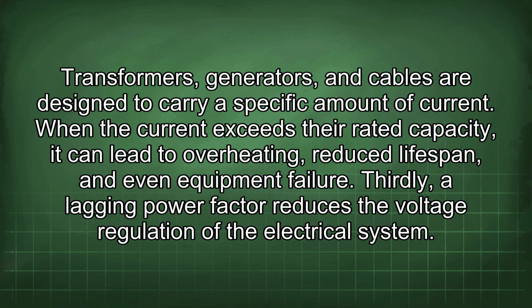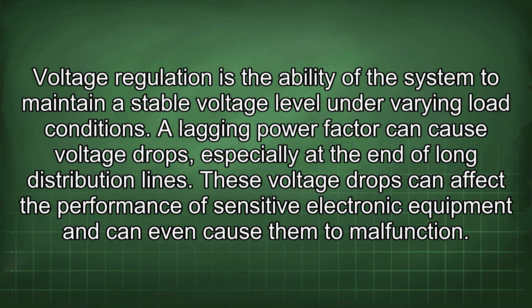Thirdly, a lagging power factor reduces the voltage regulation of the electrical system. Voltage regulation is the ability of the system to maintain a stable voltage level under varying load conditions. A lagging power factor can cause voltage drops, especially at the end of long distribution lines. These voltage drops can affect the performance of sensitive electronic equipment and can even cause them to malfunction.